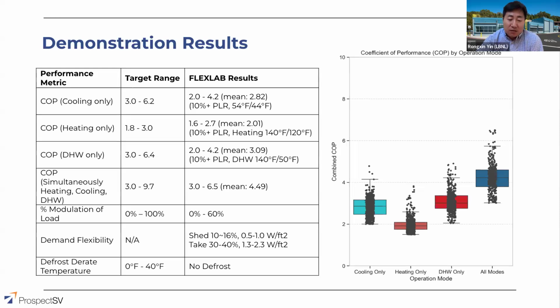Because of the oversized plant, we only tested up to 60% of the overall load conditions. We do have some data from testing in the manufacturer's facilities, and we combine that data with our laboratory testing data to fit performance curves. I'm going to describe that information later on. In addition to the performance of the unit, we also conducted a few weeks of demand flexibility testing. We implemented commonly used global temperature adjustments to see how the system and plant respond to those setpoint adjustments, and looked at a few key metrics about load shed and load take.